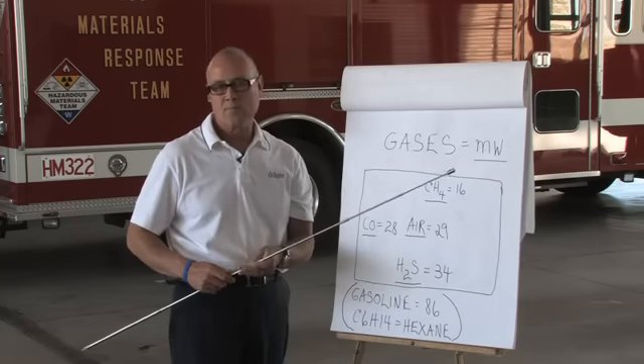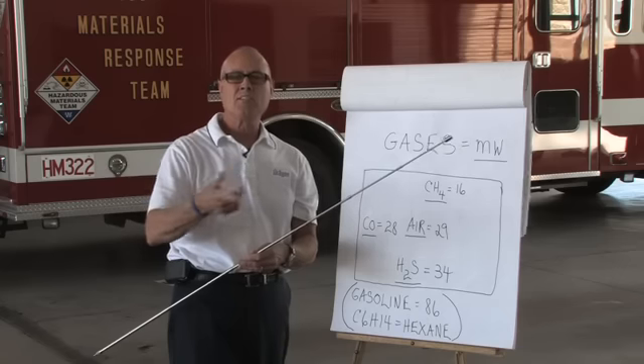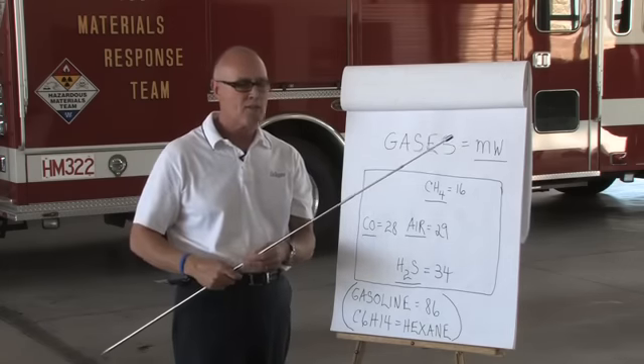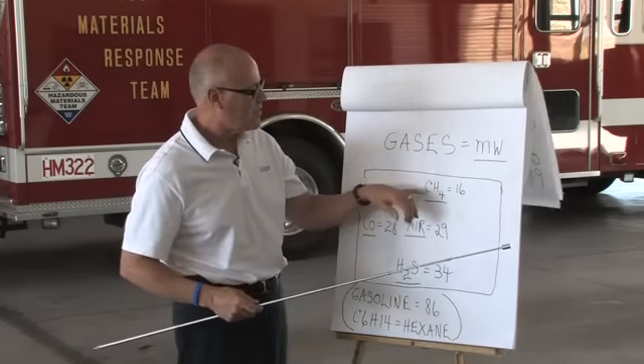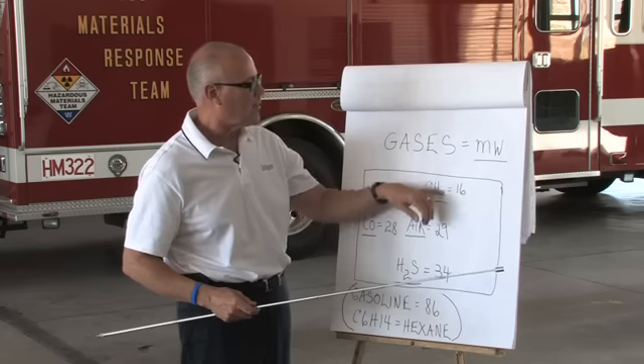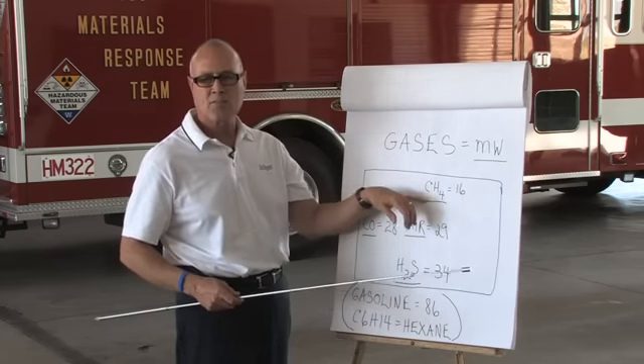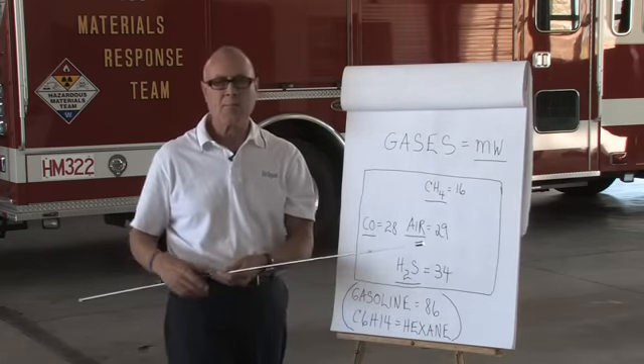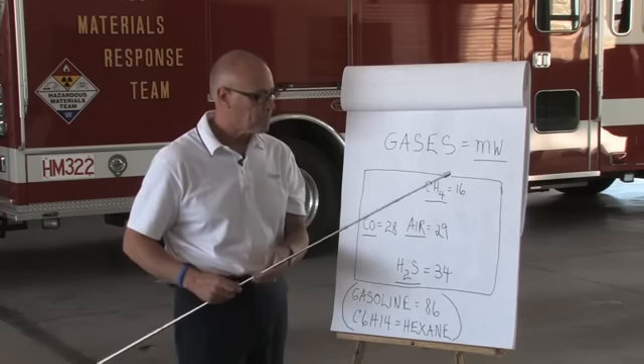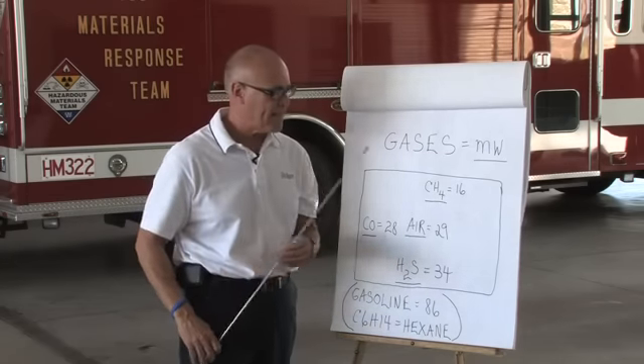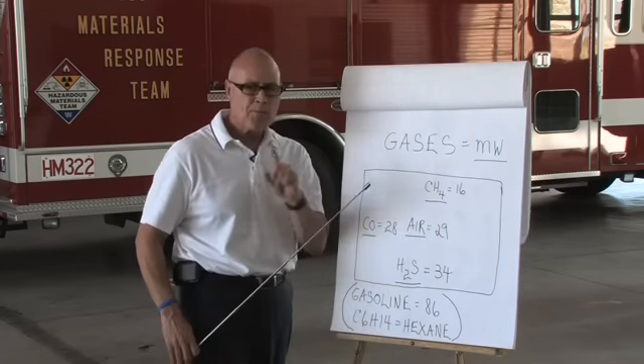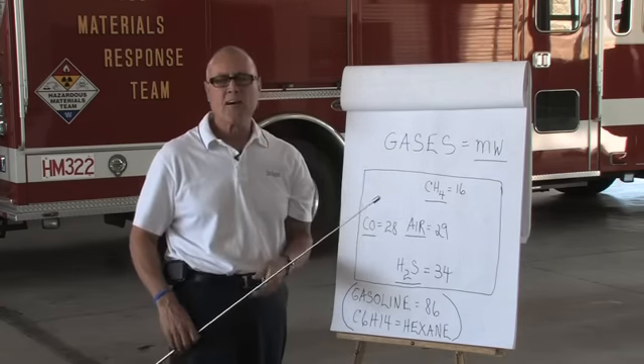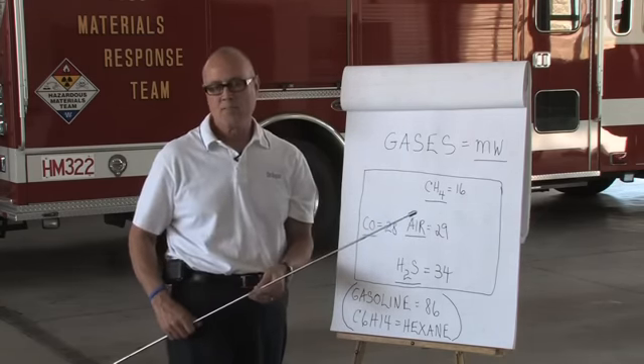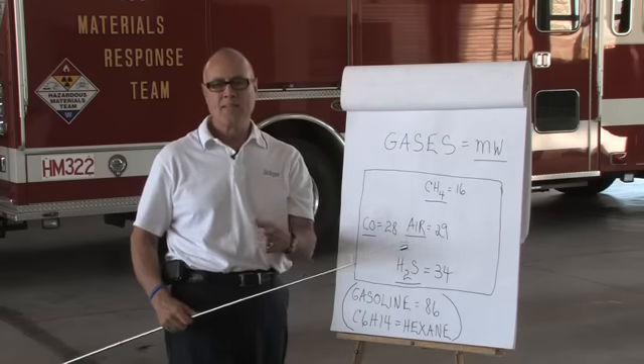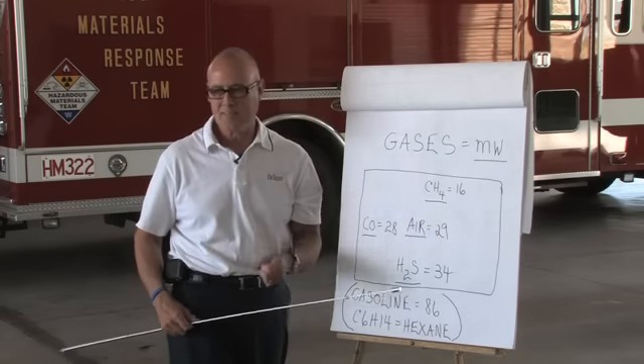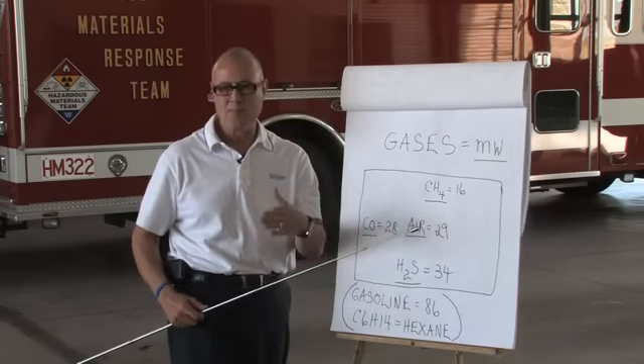to see if there's natural gas that might be hovering underneath the ceiling of a given structure. If there's plenty of convection, meaning air movement within the structure, there's a good chance, if there's quantifiably a lot of natural gas in that structure, you'll be able to pick it up on your Draeger meter. And just to give you an idea on natural gas, 1% of the LEL equals 500 parts per million. So it takes 500 ppm to get the meter to go to 1% LEL. Okay, that's how the increments go.